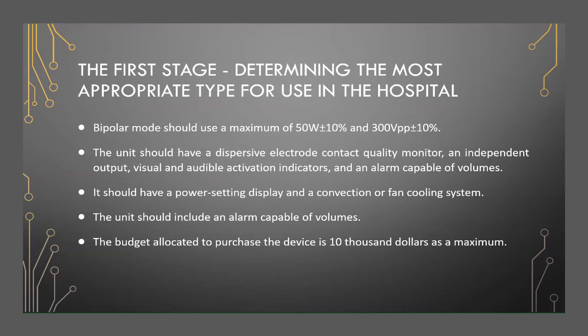The unit should have a dispersive electrode contact quality monitor, an independent output, visual and audible activation indicators, and an alarm capable of volume control. It should have a power setting display and a convection or fan cooling system. The budget allocated to purchase the device is $10,000 as a maximum.